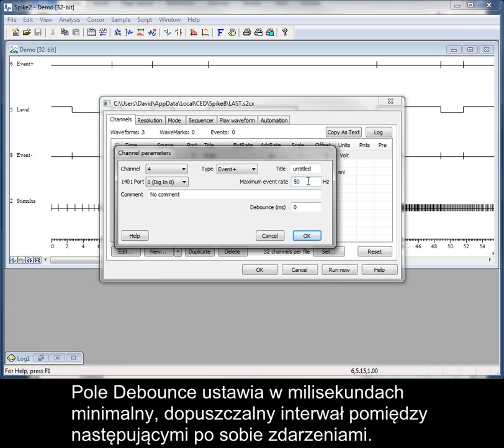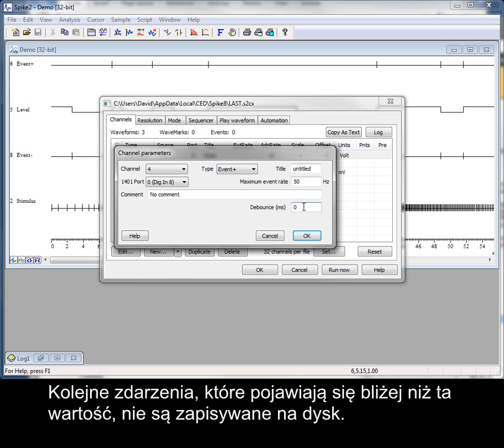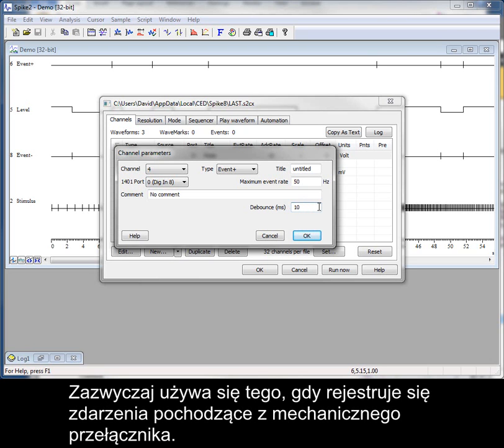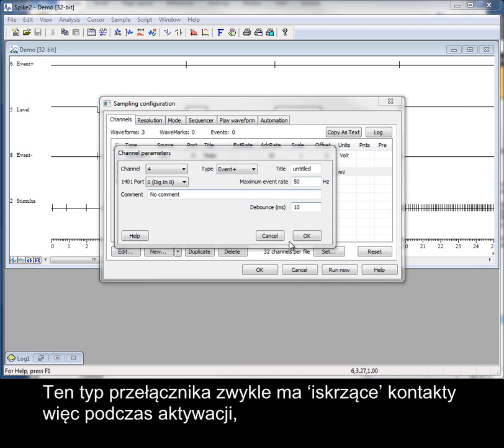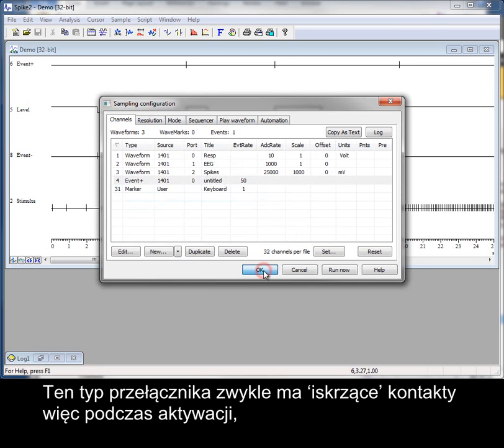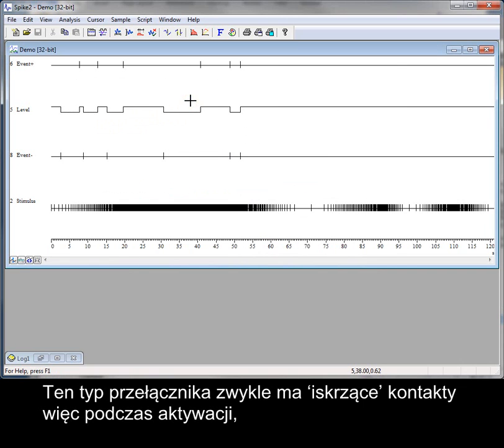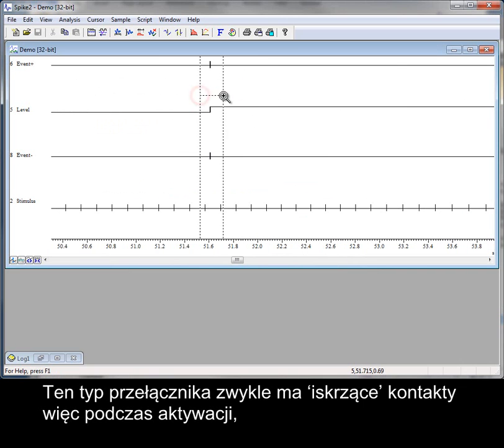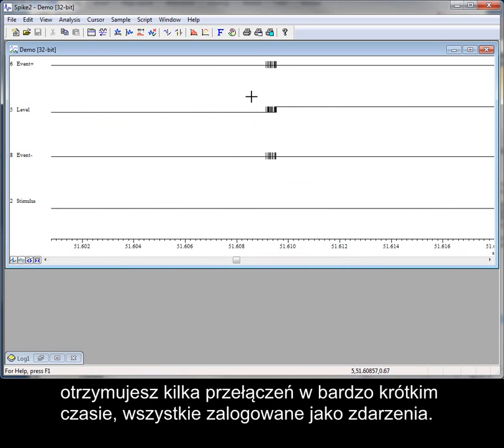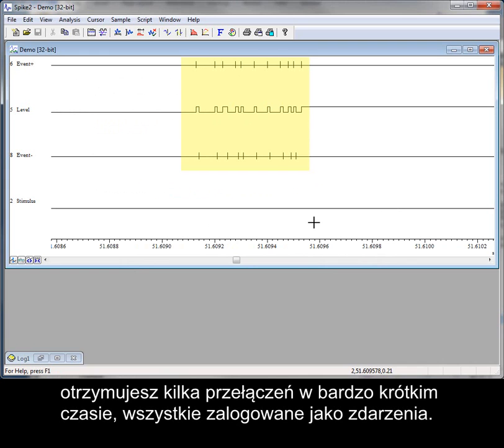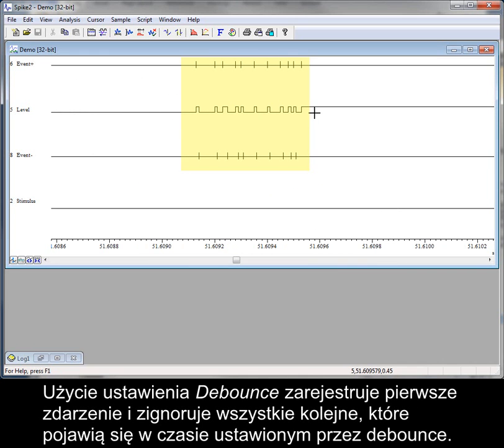The Debounce field sets the minimum acceptable interval between consecutive events in milliseconds. Events that fall closer than this value to the previous event are not saved to disk. Typically, you would use this if logging events from a mechanical switch. These types of switches commonly have bouncy contacts, so that when the switch is activated, you get multiple switch actions in a very short period, all logged as events. Using the debounce setting will log the first event and ignore all those that fall within the debounce time range.